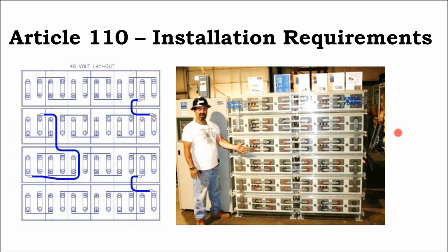You can't do that with a sealed battery because the gas stays inside the battery. And so applying a hard charge to the battery causes it to produce a lot of gas. An unsealed battery can take it, because the gas leaves the battery to be vented to the outside. A sealed battery has a reduced charging profile because they cannot be aggressively charged. You'll damage the battery if you do.